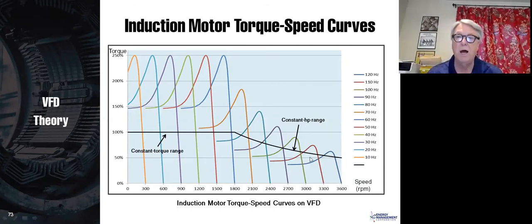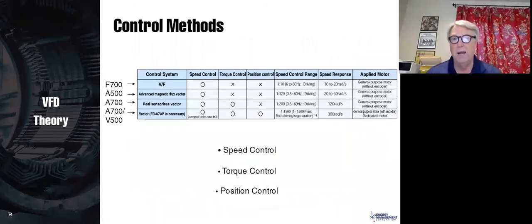If you get too high, you can get into very high currents, and you can actually stall the motor, as well as other problems due to vibration and so on, and bearings. But it's not uncommon to go a little bit above base speed, and I don't have any problem with that in general, as long as your equipment can take it, you don't get vibration, and you stay under the motor full load amps.